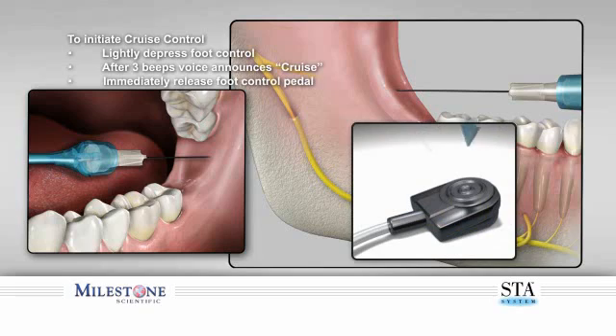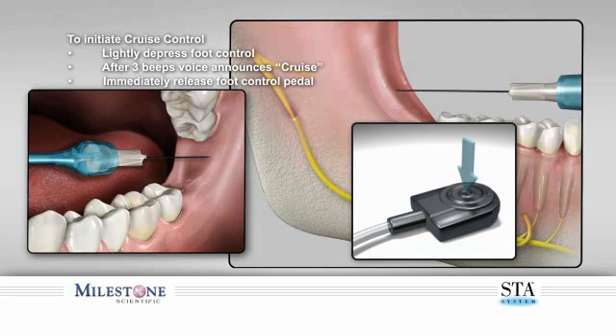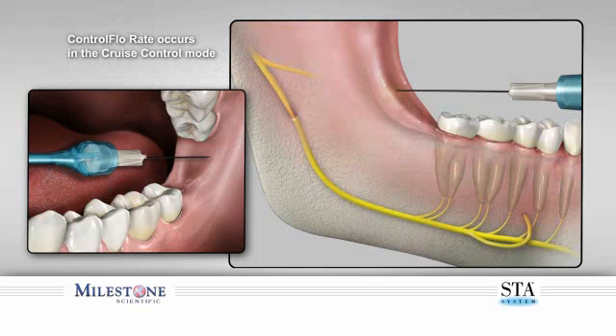To initiate the injection using cruise control, slightly depress the foot control. After three beeps, you will hear the STA system announce 'cruise.' Immediately release the foot control pedal to enter cruise control mode. This allows the ControlFlo rate to continue to dispense anesthetic solution, creating an anesthetic zone in front of the tip of the needle.